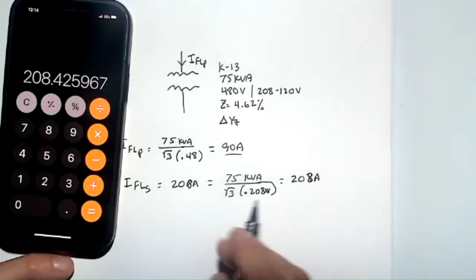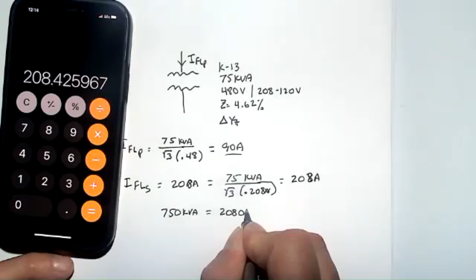How do I know that? Well, let's go ahead and multiply it out. 75 kVA divided by the square root of 3 divided by 0.208 kV, because it's 0.208, and we get 75 divided by 1.73 divided by 0.208, and that works out to be 208 amps. If you can remember that a 75 kVA 208 volt transformer gives you 208 amps, so 208 volts and 208 amps, what would be a 750 kVA transformer? Well, then it's 208 times 10, or 2080 amps.